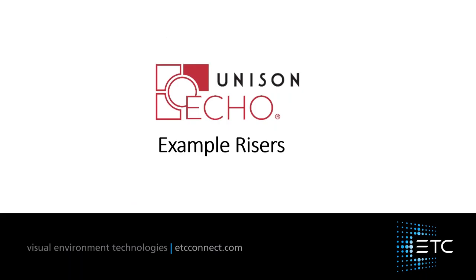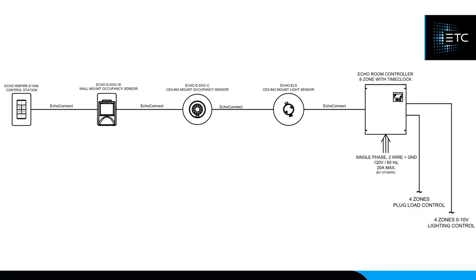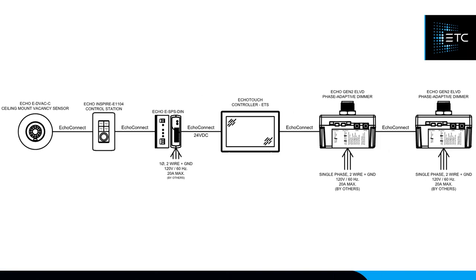A basic ECHO system, reading left to right: an ECHO button station with a built-in sensor, a 6U power supply, and a 0-to-10V controller — that's it, you can turn your lights on and off. Expanding that, you can tie in multiple control devices into a room controller: a button station, a wall occupancy sensor, a ceiling occupancy sensor, and a light sensor, all controlling up to eight relay zones together or independently, with the light sensor affecting only specific zones.